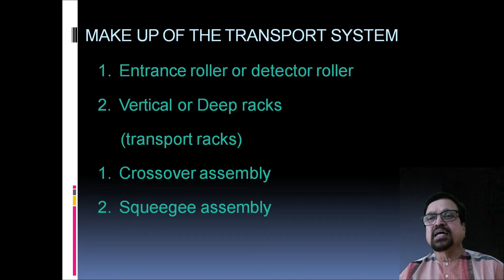Now, the makeup of the transport system: entrance roller or detector roller, then vertical or deep racks, that is the transportation rack, crossover assembly and squeegee assembly. Now it is shown in this section, that is the cross section of an automatic processor. The entrance roller grabs the film and draws it into the developer. The entrance rollers separate slightly, the film passes between the rollers, activating micro switches controlling replenishment of the chemicals. So that will maintain the level and also the adequate concentration of the chemicals.